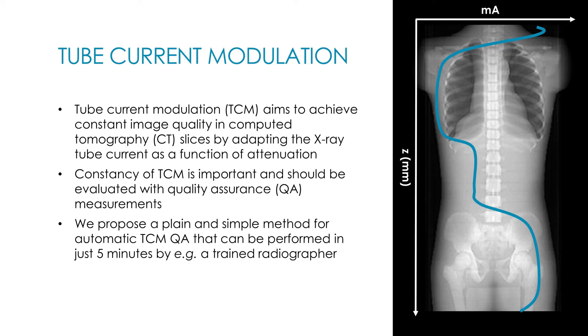As you know, tube current modulation is an integral part of any modern CT scanner as it improves patient dose optimization and allows standardized image quality in each CT slice in the acquired imaging data. As such, constancy of TCM is an important factor to keep track of in the quality assurance program.